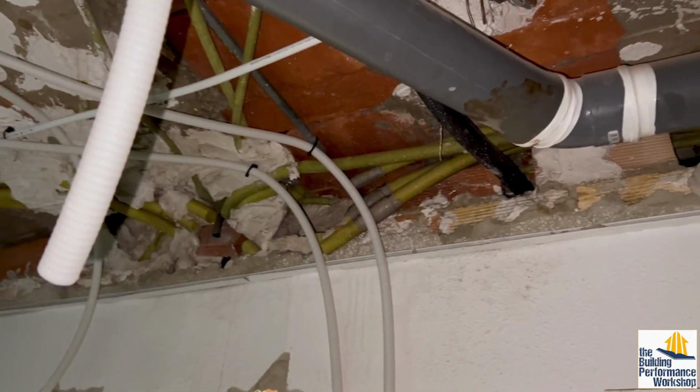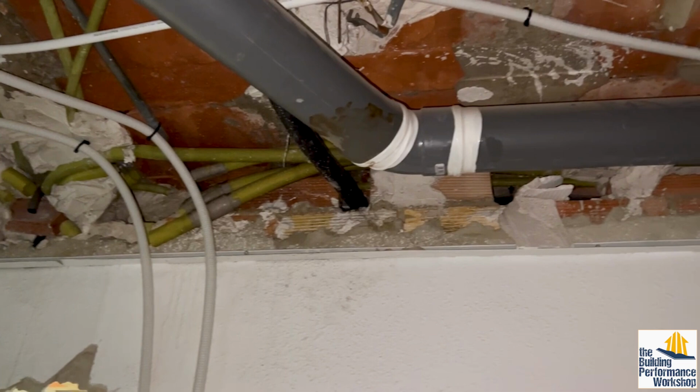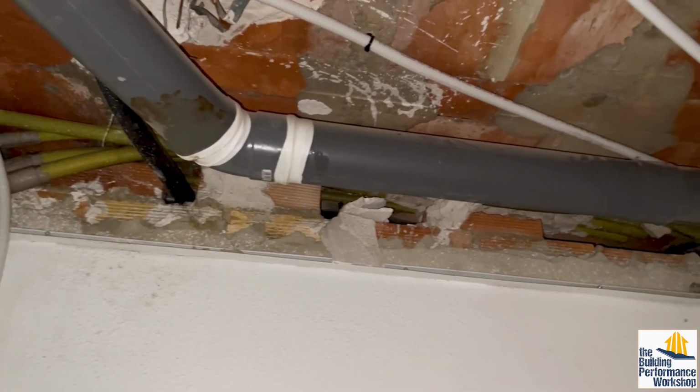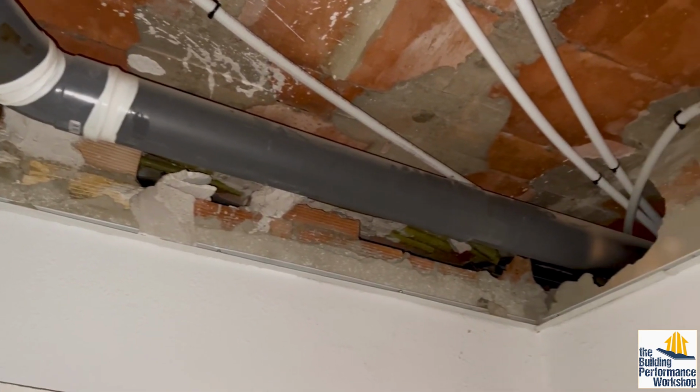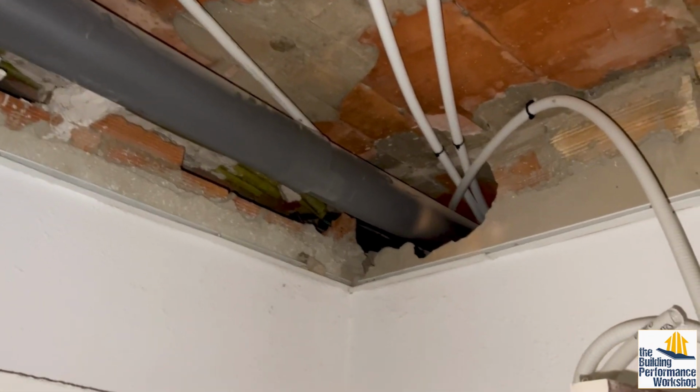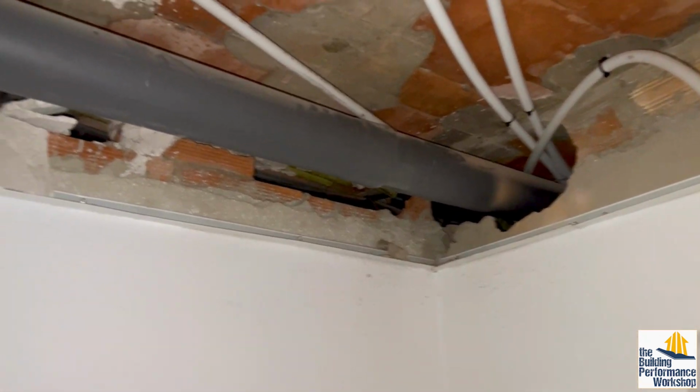The other thing that happens is that we are depressurizing the whole ceiling cavity. And that means that this sewer gas smell that we're concerned about could be coming from literally anywhere, because it's all going to be drawn back to the unit. Like I said, this smell mostly happens when the AC is running. So it's definitely related to the AC depressurizing on that ceiling plenum.